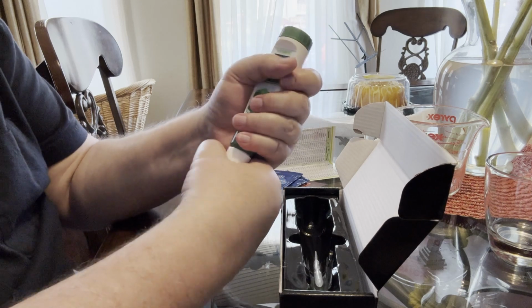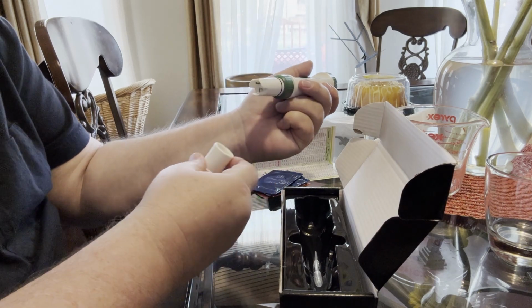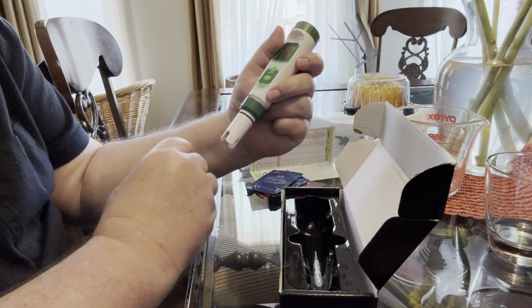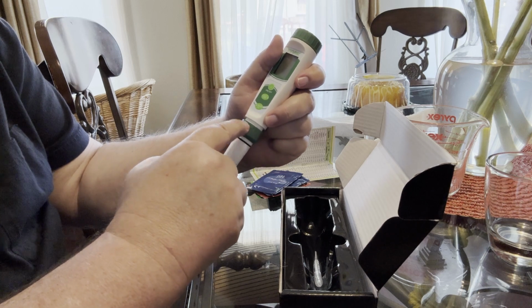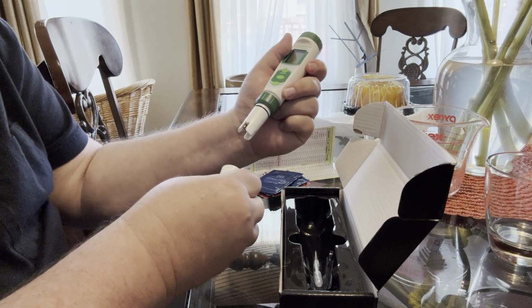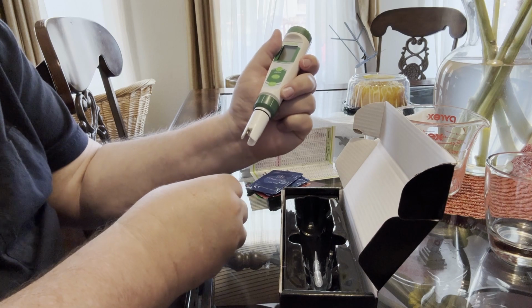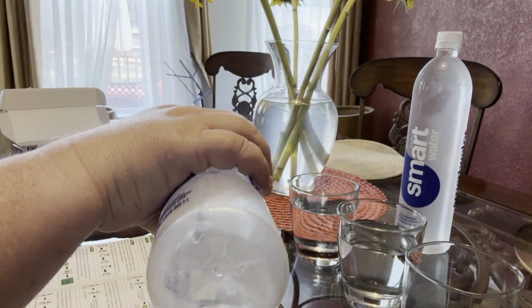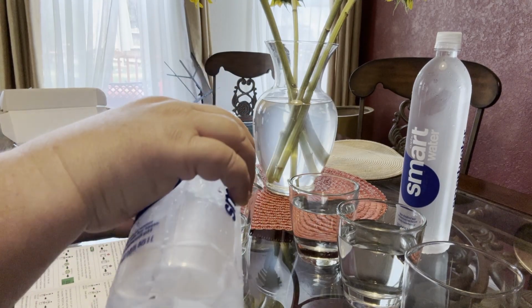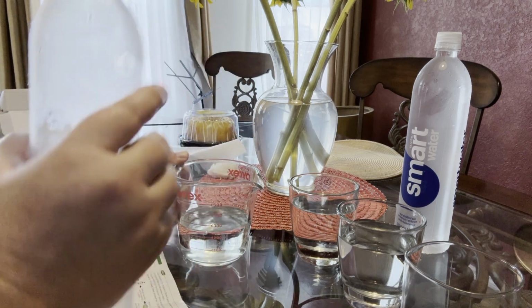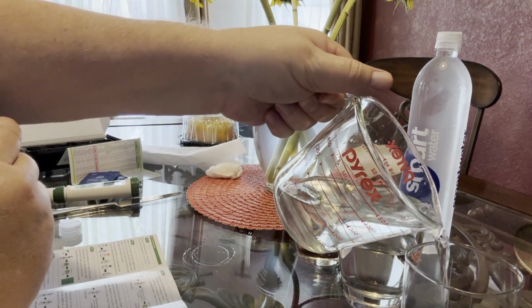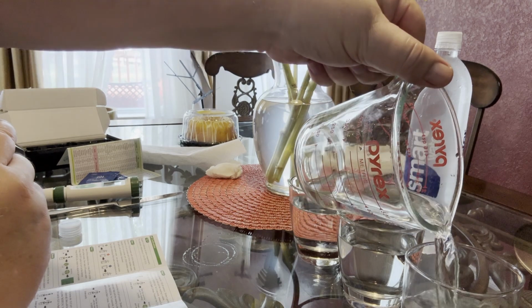Okay, the unboxing is done. Let's calibrate the meter for pH and review the features at the same time. The meter is calibrated at the factory for ppm, so I will only calibrate for pH at this time. Let's start with the calibration for pH, and I will touch on a few of the features and functions along the way. A couple of tips before we start.